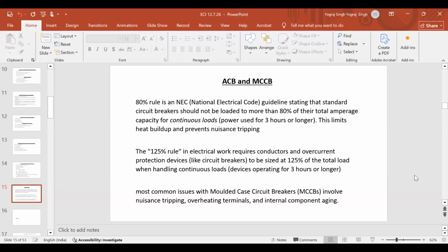Okay, I'll proceed. Then there is the reciprocal of this, which is the 125% rule. It means if my load is 400 kVA, the transformer I will put is 500 kVA. You must have seen the plug point in your home where you use an iron press or other things. Though the power point is rated 10 ampere, the current through that power point never goes to that rating. But over a period of time, you will find that the power point has burnt. It has burnt because that cushion is not available to the power point.